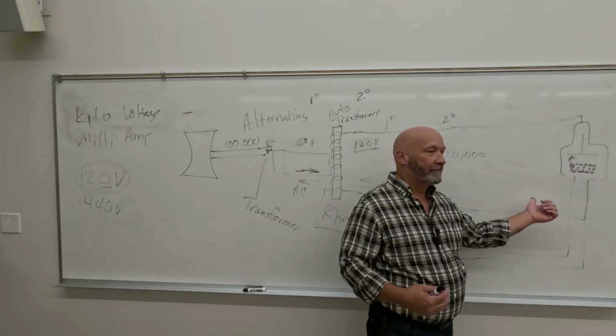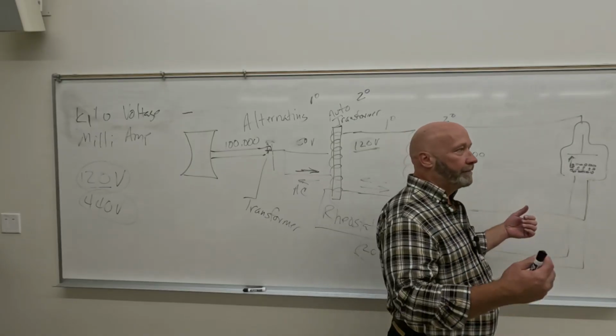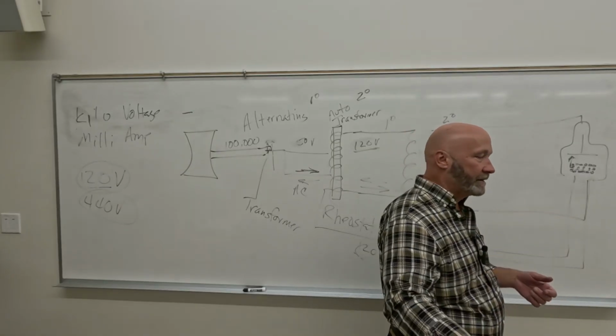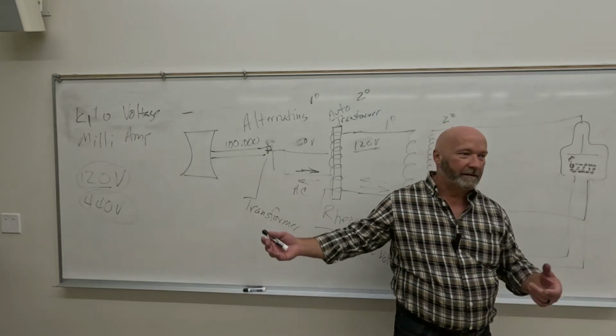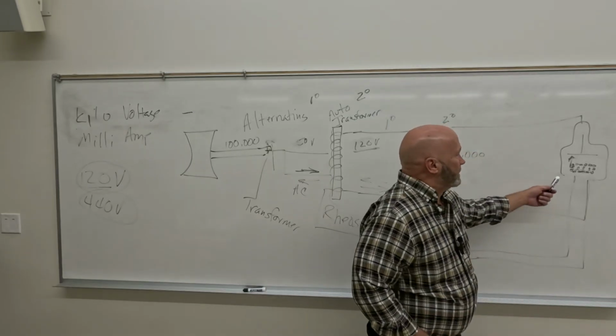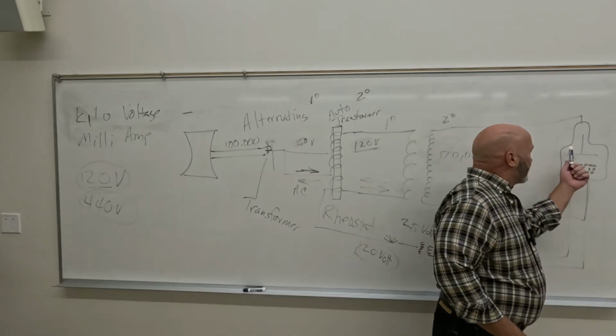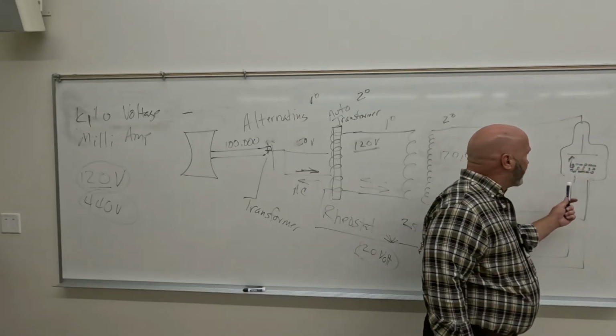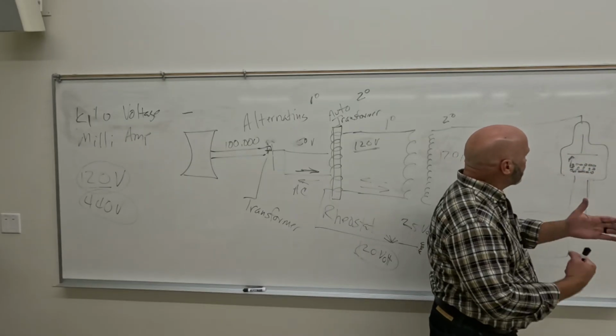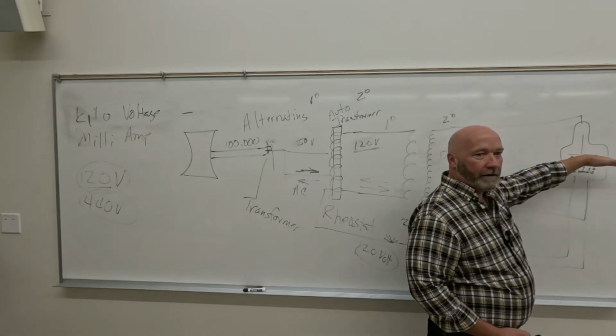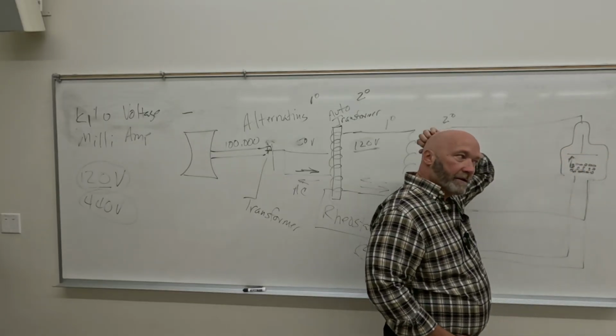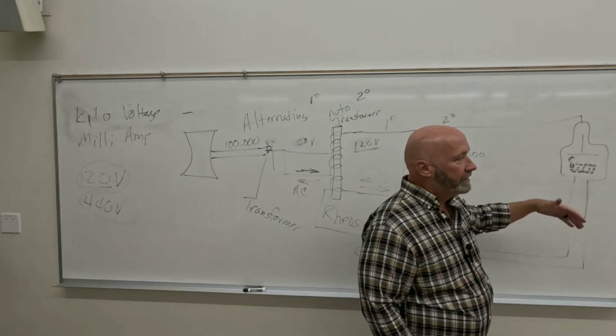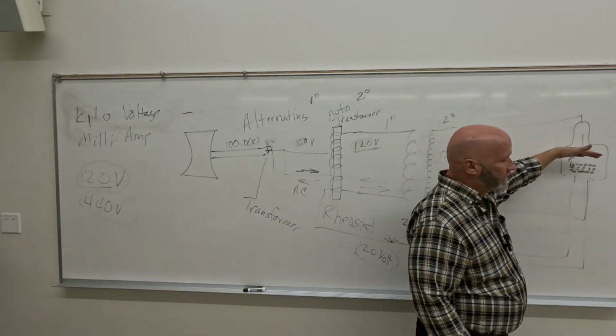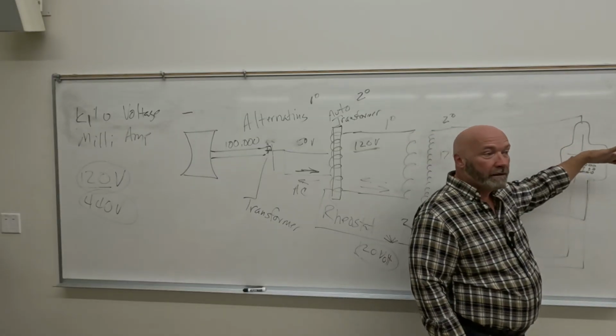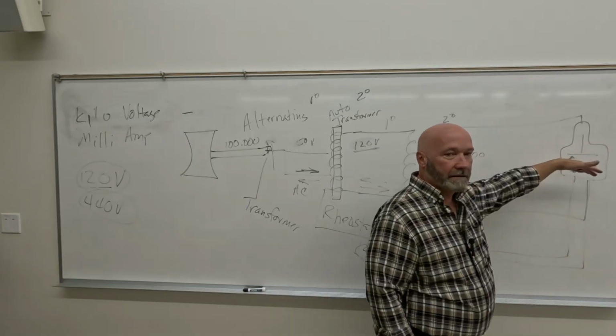kVp does a lot of stuff. We've got a lot of names for kVp: potential energy, electric potential, penetration, just a lot of stuff. So at this point, once we press the exposure button, the electrons travel across the tube and they smack into this thing really, really hard. They're traveling really fast. The upper register of the speed is maybe a third of the speed of light. They're really, really moving fast, okay?